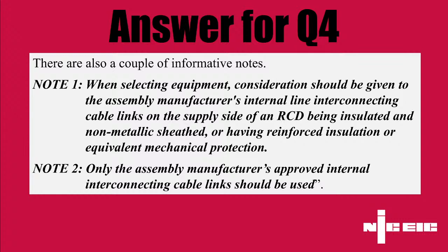Well, it does depend. On a dual RCD board that has single insulation on the RCD links, providing that's the manufacturer's instructions, and there are obviously no signs of damage on the links and they're not likely to come into damage, that would still be acceptable without having 100 milliamp at the head. Quite often people think, if I replace the main switch with an RCD, then I'm doing it well. That would only really protect the internal cables supplying the final outgoing circuits, and those are part of the manufacturer's instructions on the board or consumer unit anyway. So that doesn't really do much, providing of course you've got all of your outgoing circuits RCD protected. So yeah, it's not a requirement.